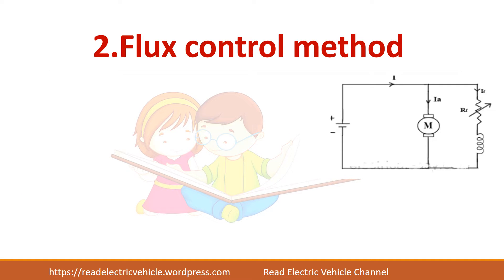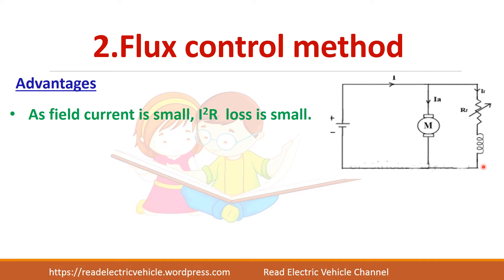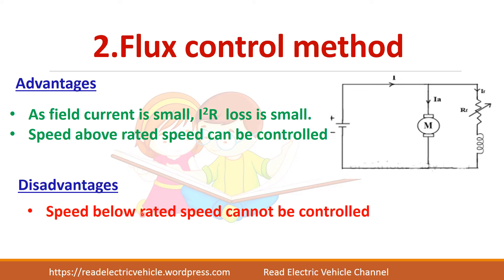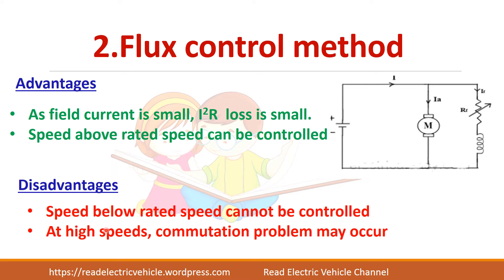The advantages of the flux control method are that the field current will be small, so the I-squared-Rf losses will be small, and you can achieve speed control above rated speed. The disadvantage is that you cannot get speed control below rated speed. Another thing is that at high speeds, because we are reducing the flux and increasing the speed, you may get commutation problems.